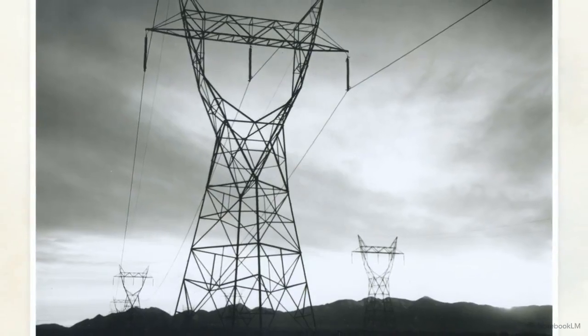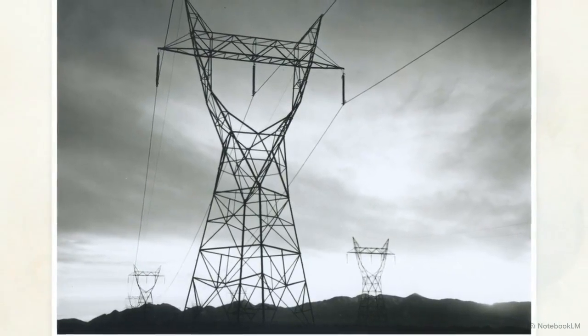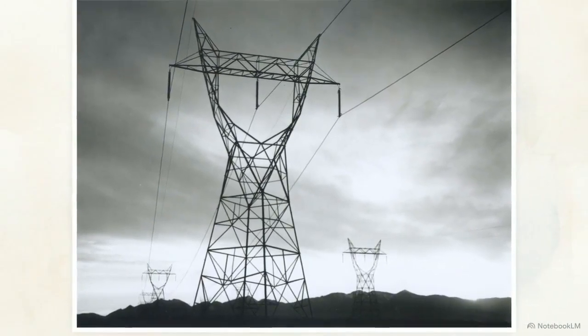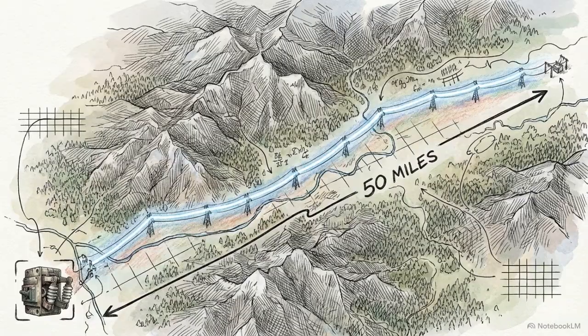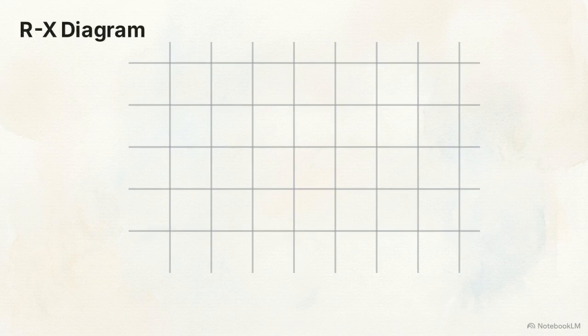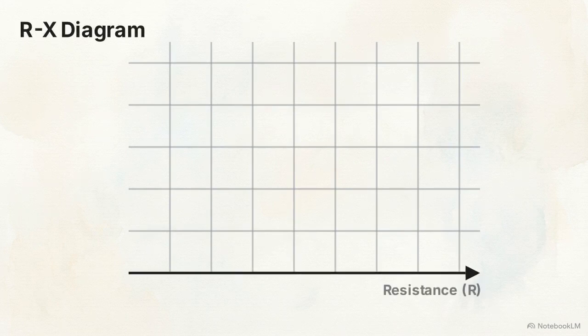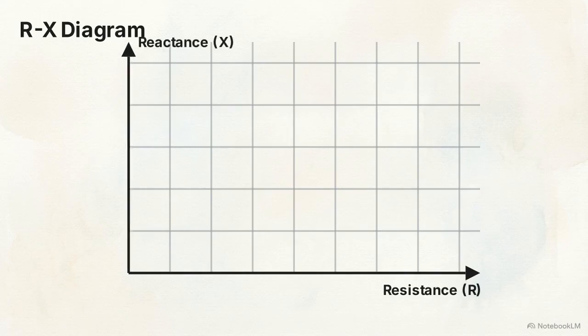Protecting generators is straightforward, but protecting miles and miles of outdoor power lines requires a different logic. A relay can't measure both ends of a 50-mile line at once. Instead, it acts as a distance relay. To figure out exactly how many miles away a fault is, the relay plots electrical data on a map. This empty chart is an RX diagram. The horizontal axis measures resistance, and the vertical axis measures reactance, two ways the wires push back against electrical flow.